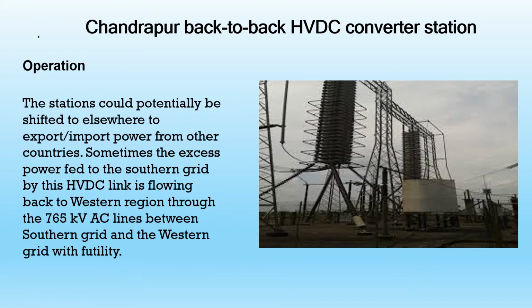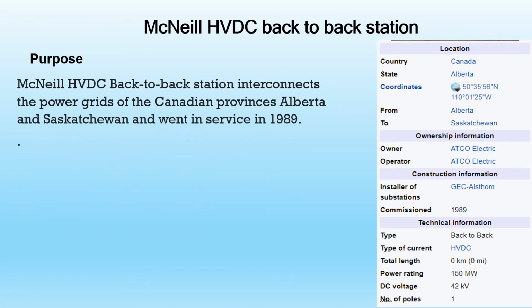The station could potentially be shifted elsewhere to export and import power from other countries. Sometimes the excess power fed to the southern grid by this HVDC link flows back to the western region through the 765 kV AC lines between the southern grid and the western grid, with futility. Now let's see the McNeill HVDC back-to-back station.